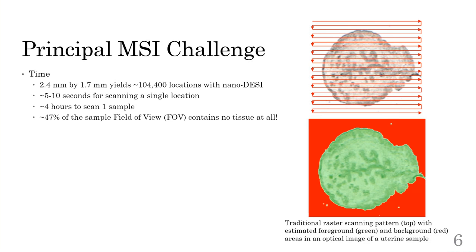MSI in general obtains rather absurdly large quantities of molecular information, and it's become both a unique and critical tool in medical research. However, this comes at the price of time investment. Each single position in the sample can take upwards of 10 seconds to actually measure. This means that to use nano DESI on a sample, such as the uterine section shown on the right, processing over 104,000 locations takes roughly four hours. This is in large part due to the reliance on a traditional raster scanning pattern, which obtains not only data irrelevant to an experimentalist's objectives, but also background information. For the sample shown, roughly 50% of the total area contains no tissue at all, suggesting a clear potential for throughput to be doubled without any losses.